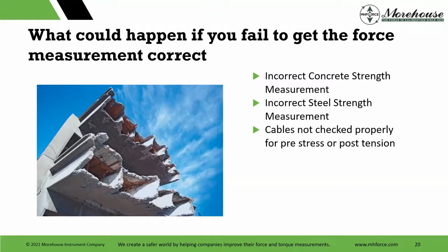So 22 people online. I'm going to ask a question. I have a 10,000 pound device with an accuracy of 0.1% of full scale, plus or minus 10 pounds. My calibration certificate says the unit reads 10,000 pounds when 10,000 pounds was applied. Is my device in tolerance?